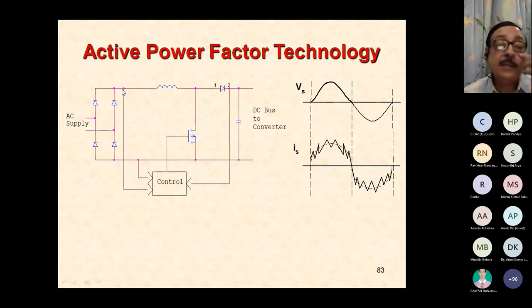Although here I have shown that I'm monitoring the DC bus voltage, the current on the input side at any instant is the same as the DC current, because there is no parallel path in between. So input current will be almost sinusoidal like this in both the half cycles. Now we have the diode to prevent the capacitor from discharging into the switch when the switch is turned on. So that's the blocking diode. And second thing is, the output voltage is always higher than the peak of the highest AC supply voltage. Because only if this voltage is higher than the peak of the supply will these four diodes be naturally reverse biased. If they are, only then can this system work. Otherwise, if the voltage is held less than the peak of the supply, these diodes will have a tendency to conduct naturally, which will make the input current non-sinusoidal and beyond your control. So that is why this voltage has to be higher than the peak of the input supply.